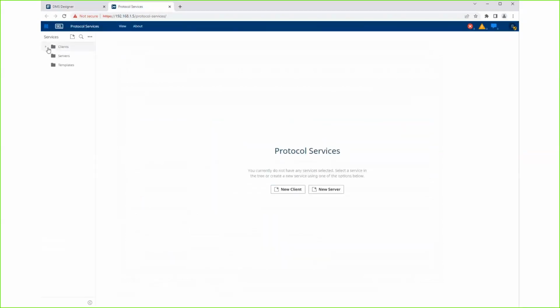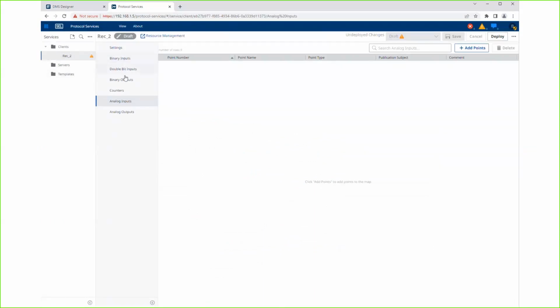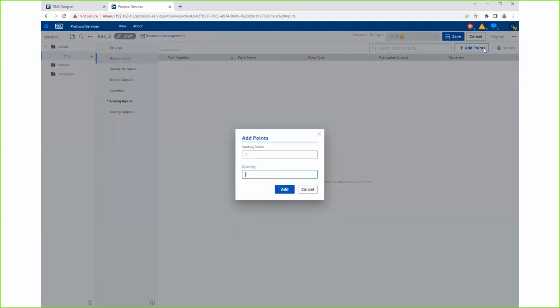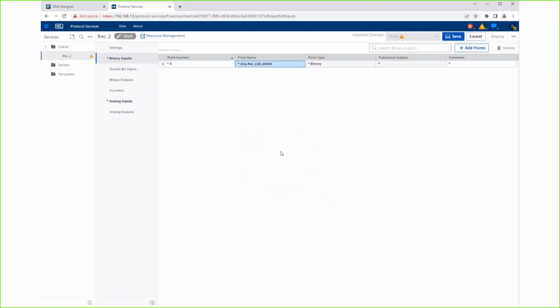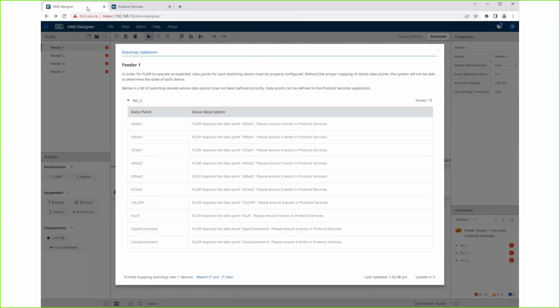So I'm going to go over to the Protocol Services tab, locate Recloser 2, and we're going to add some analog inputs. I'm going to add 3 points. I'm going to call them IA, IB, and IC, and I'm going to save these settings. So we'll add 52A3P as well. So this is three-phase breaker status. So all I'm going to do is save this DNP connection settings and go back to DMS Designer.